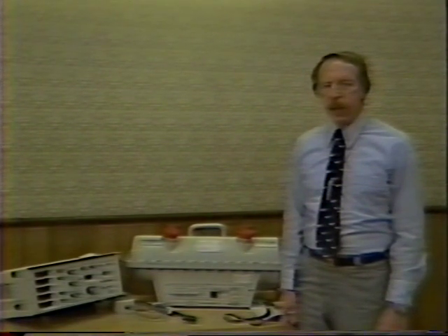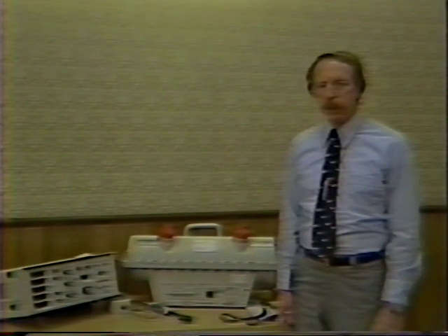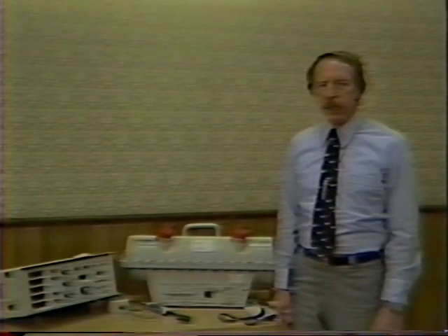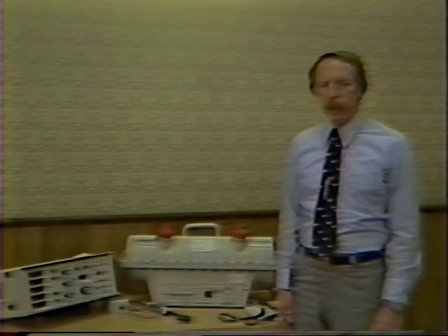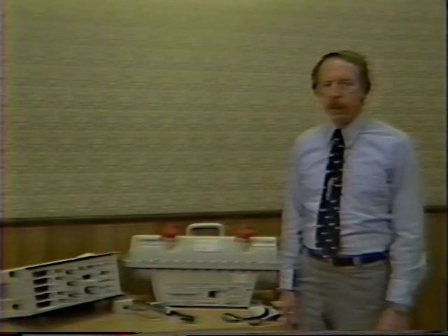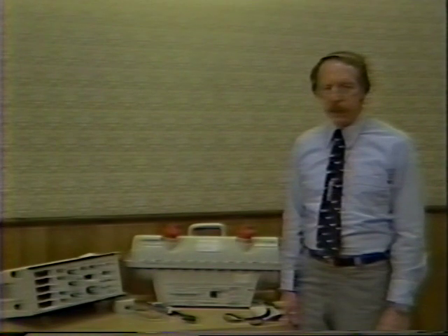Recognizing the need for quick, accurate testing of X-ray equipment, we believe that the Dynalyzer 3 microprocessor-based X-ray calibration system is a very effective device to be used by original equipment manufacturers for debugging production equipment, final calibration, compliance testing, staging, and installation, for X-ray dealers, for installation, calibration of equipment, and servicing, for hospital personnel, for periodic calibration of equipment, servicing, and quality assurance programs.